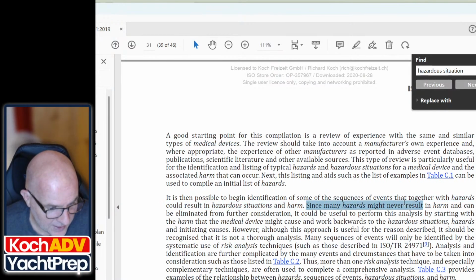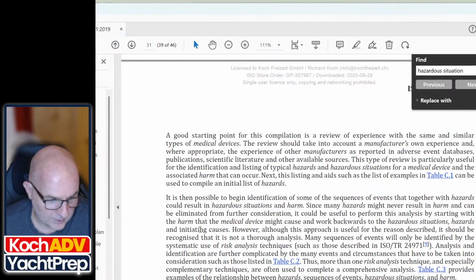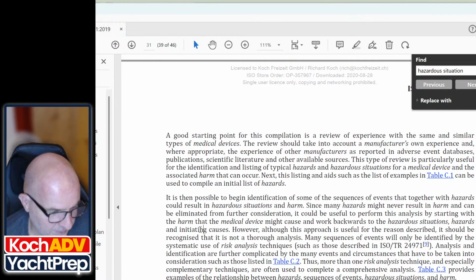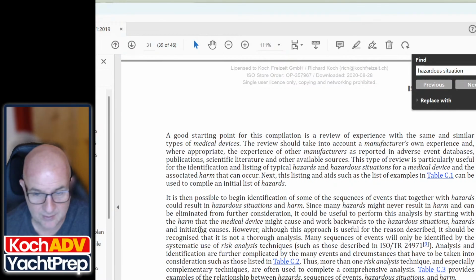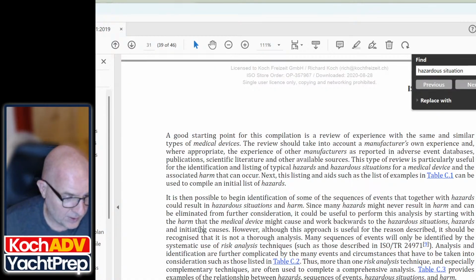Since many hazards might never result in harm and can be eliminated from further consideration, it could be useful to perform this analysis by starting with the harm that the medical device might cause and work backwards to the hazardous situations, hazards, and initiating causes, right? So, I think the general point here is if you cast the net too wide, you're not going to catch anything. So let's start with something that is actually going to be harm. However, although this approach is useful for the reasons described, it should be recognized it's not a thorough analysis, right?